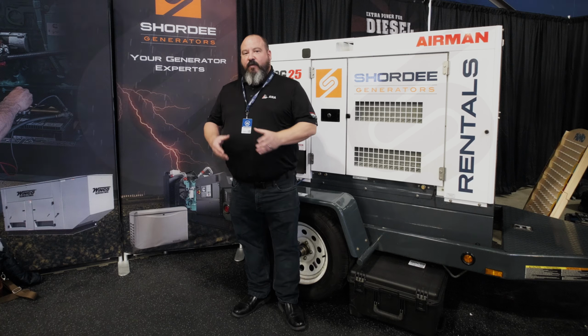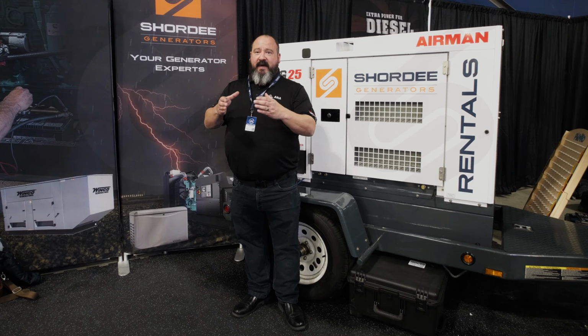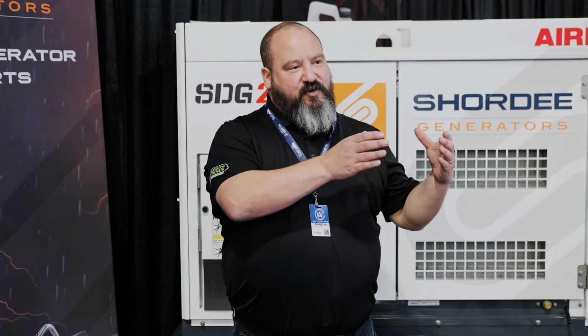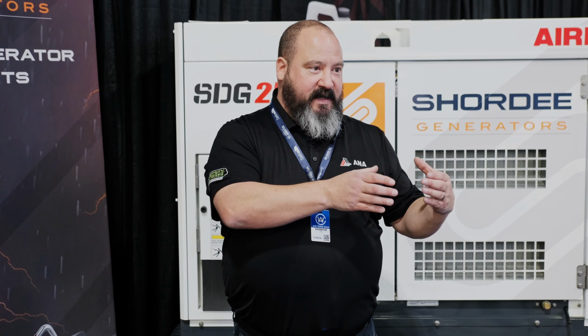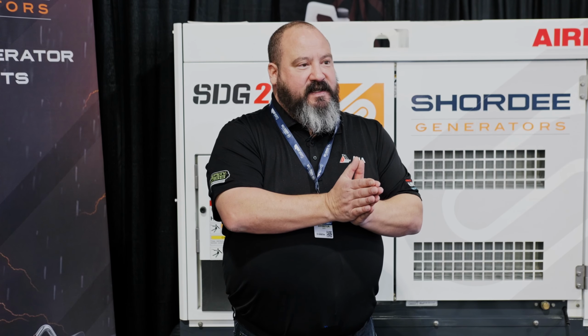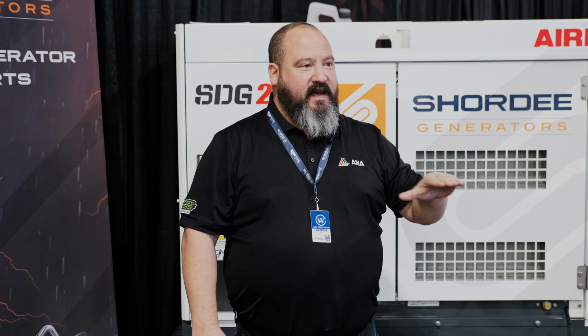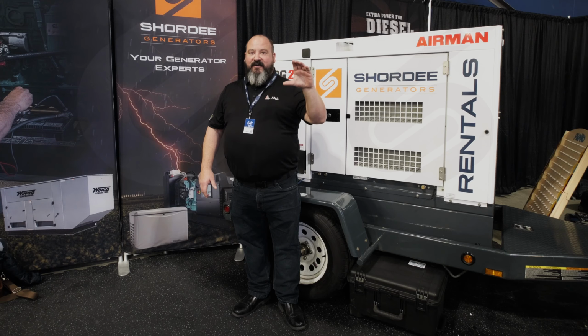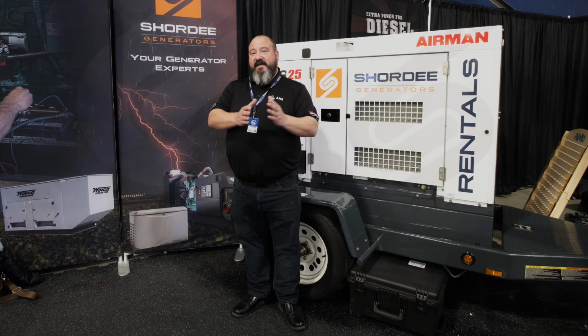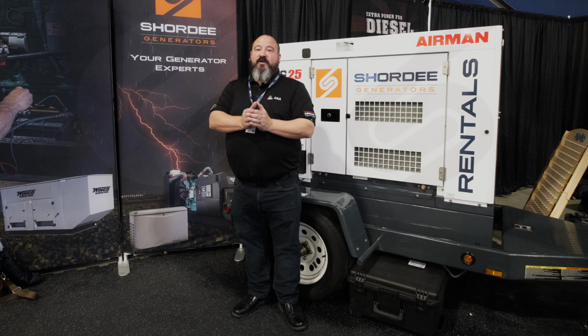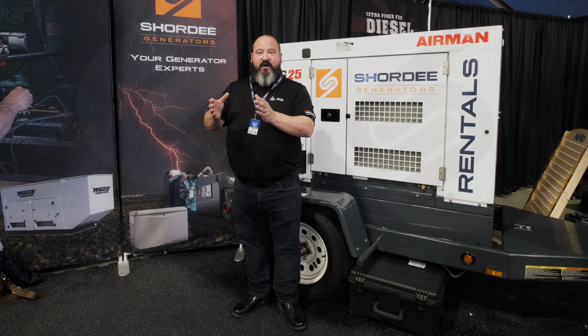With the battery system, the generator now becomes a battery charger. Everything is being drawn off of the battery. The generator is there to charge the battery, okay? What that does for us is, because you need those high peaks, you generally have to size your generator larger than your small load. The battery does not mind those high peaks and will operate at that low load for a long period of time. It does a couple things for us that we really like. One, it totally eliminates wet stacking. The generator, when it charges, does so optimally, okay?